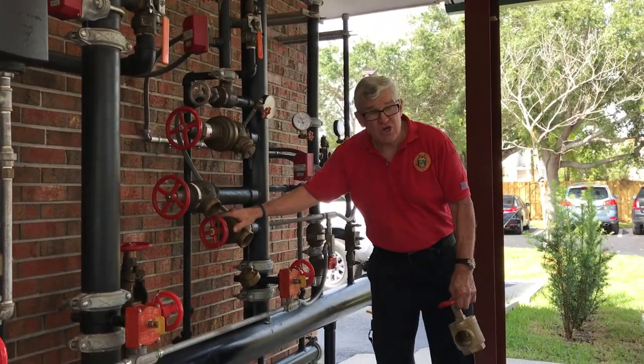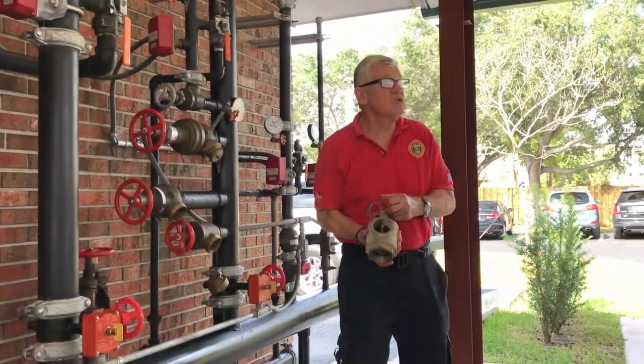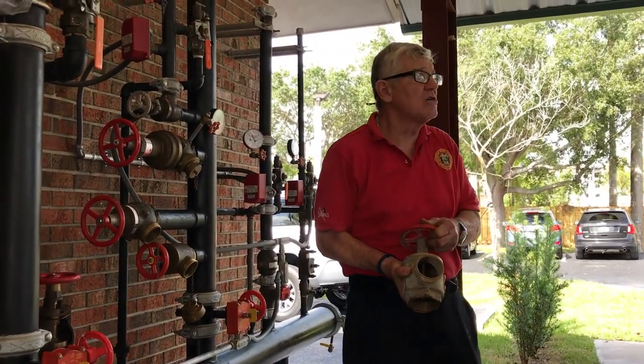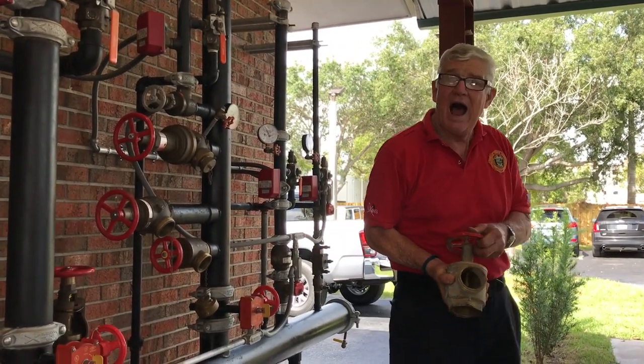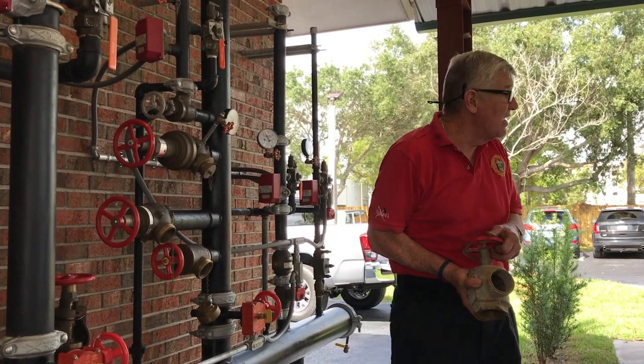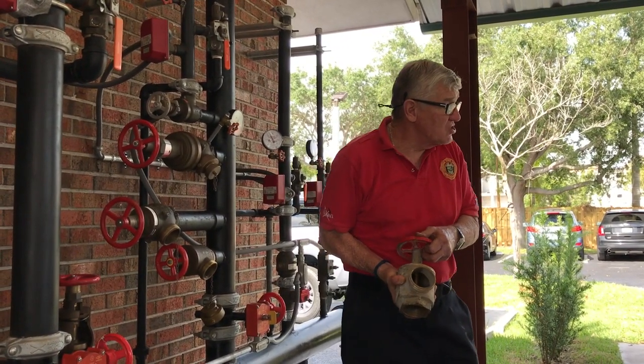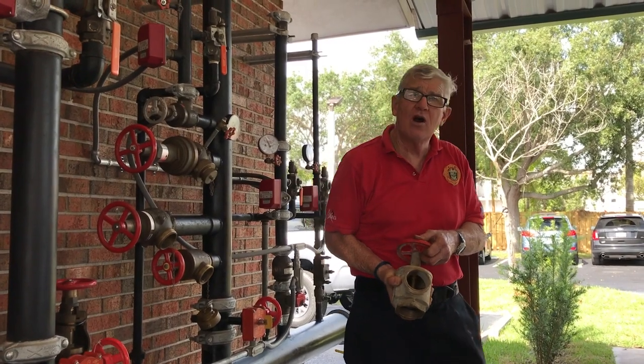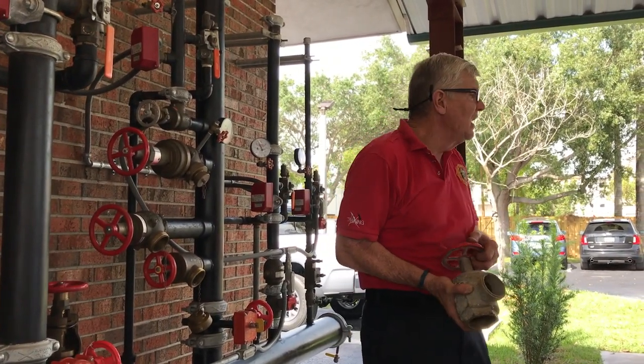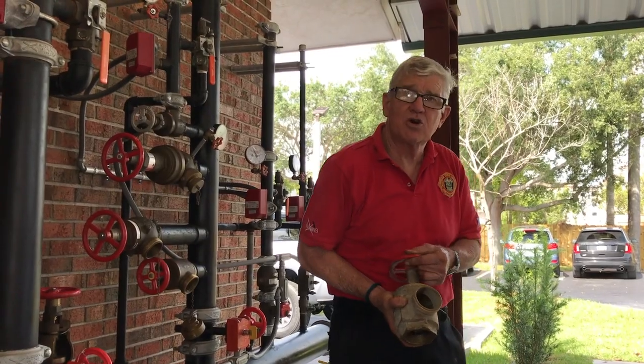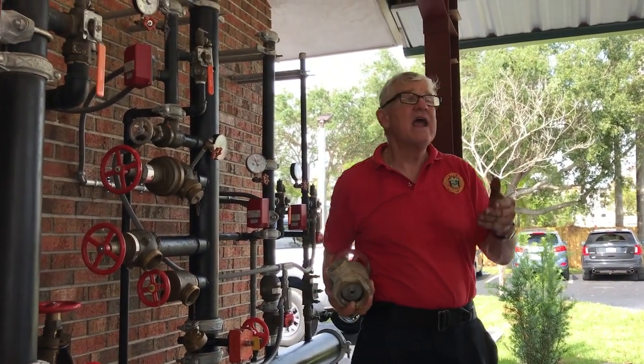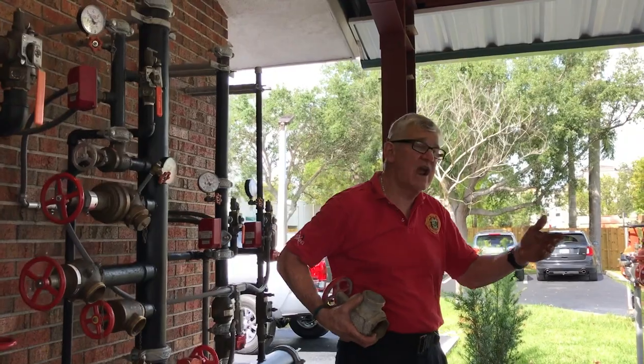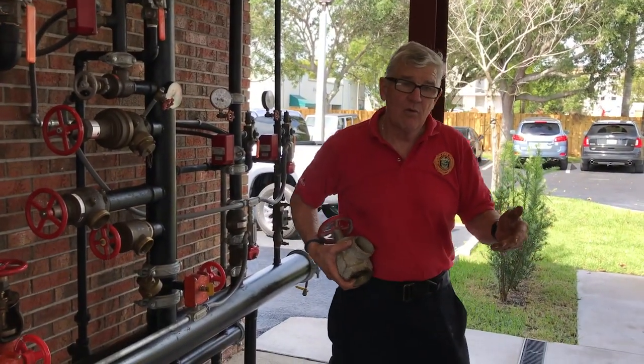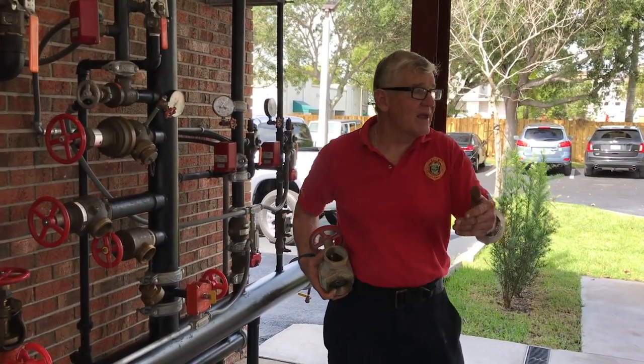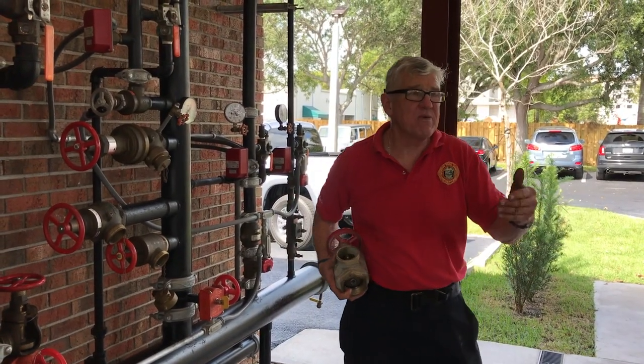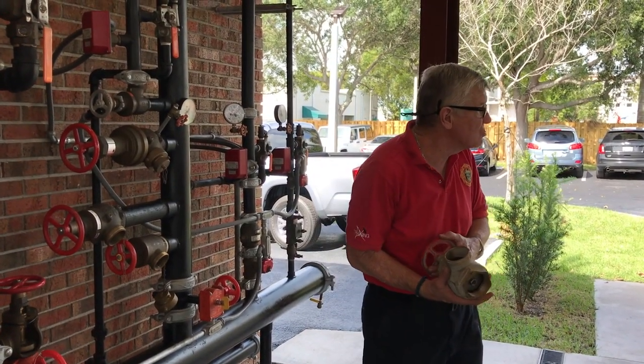So, conventional outlets are for systems that do not exceed 175 PSI on the outlet side. If the system is over 175 PSI, it has to have some type of pressure reducing device. Let me explain that again. NFPA 14, which is our standard for standpipes, requires that pressures do not exceed 175 PSI on standpipe hose outlets.